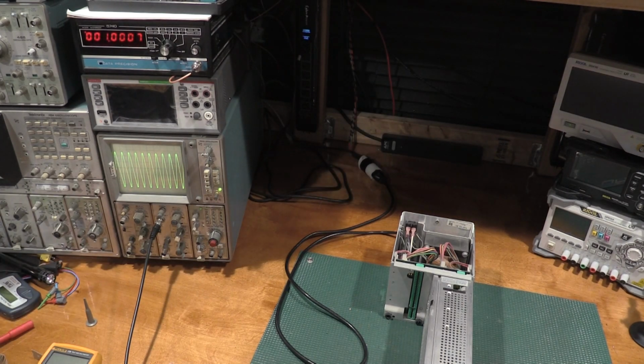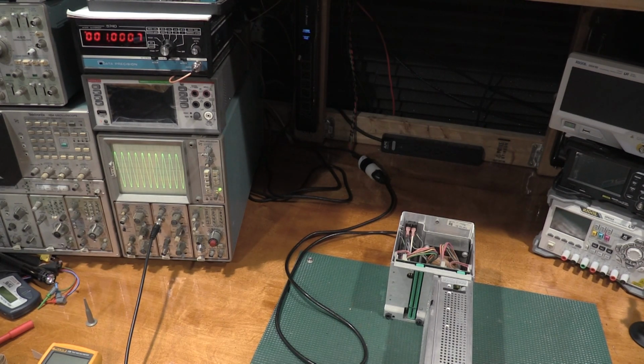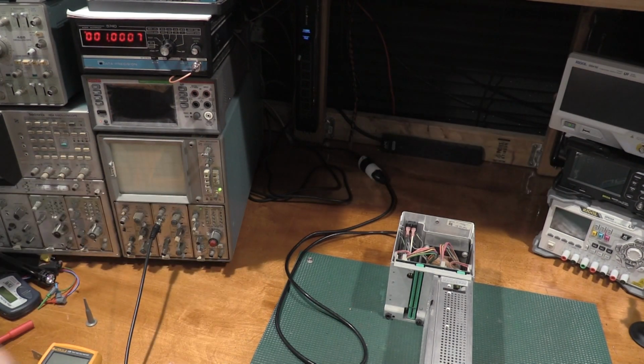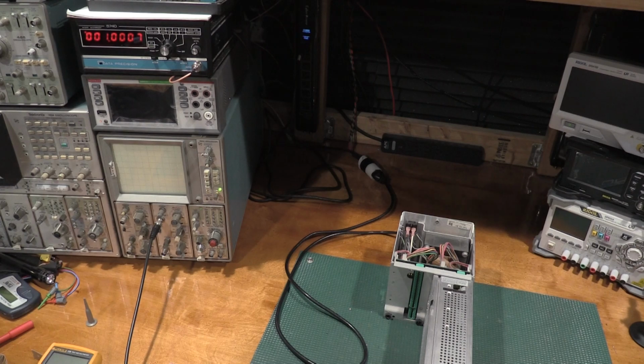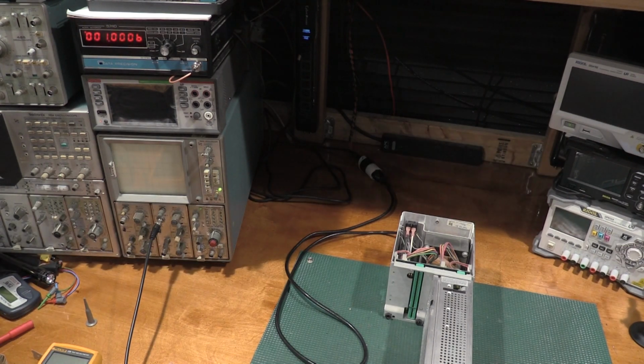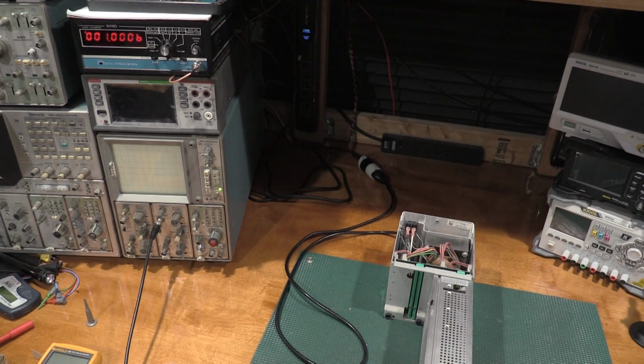I'm going to throw this up in my TM5006 power frame. And I'm going to do 2 experiments at once. One, we're going to check the distortion on the AA501A. And the other one, we're going to check whether the recap of the unit gives it stability in that particular power frame. I was having some trouble with this unit in the switch mode power supplies. It was giving me a little bit higher distortion than it should have been. So hopefully the recap will have fixed that. We're going to test both at the same time.